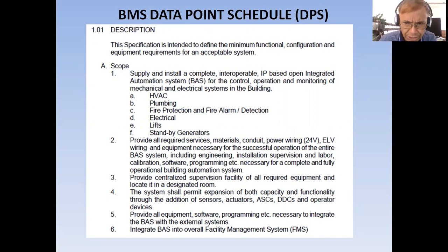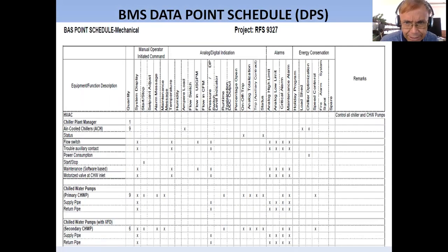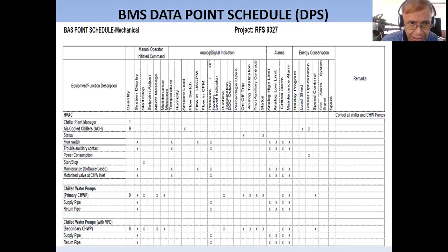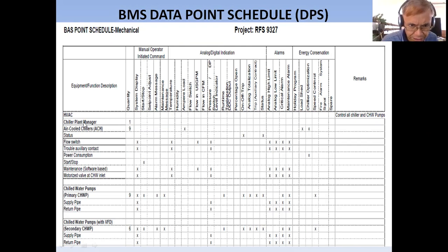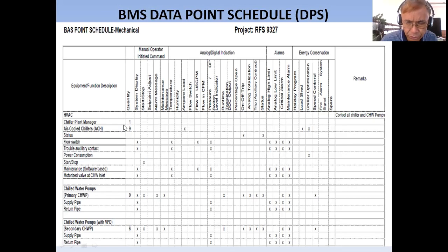Let's go directly to the defined BMS DPS in the specification. The first item under mechanical is HVAC — Heating, Ventilating, and Air Conditioning. They need a chiller plant manager, quantity one, which will control nine units of air-cooled chillers. The data points listed include status, flow switch, trouble auxiliary contact, power consumption, start/stop, maintenance, software-based motorized valve, and more.